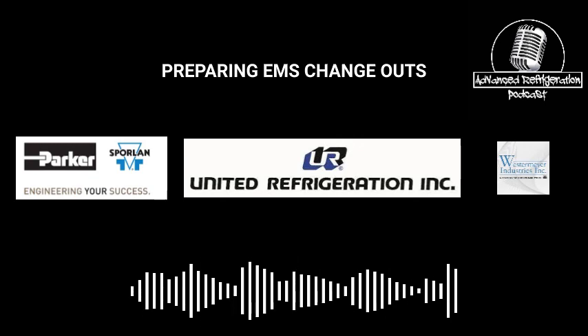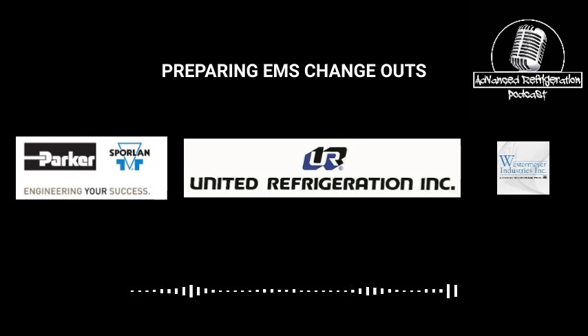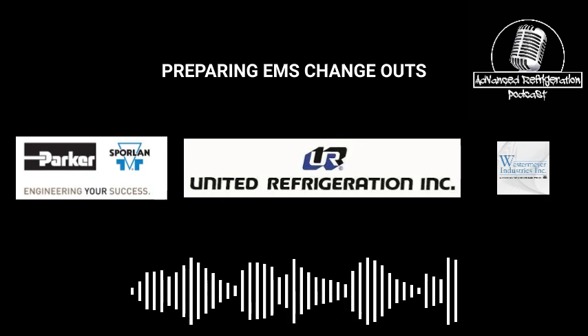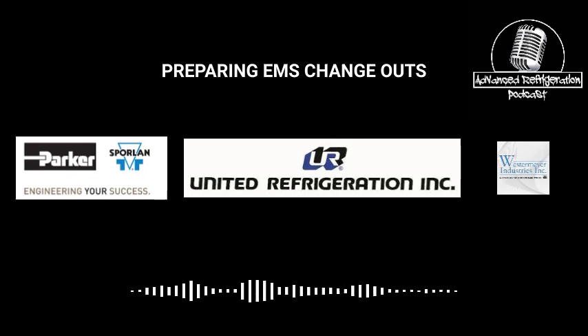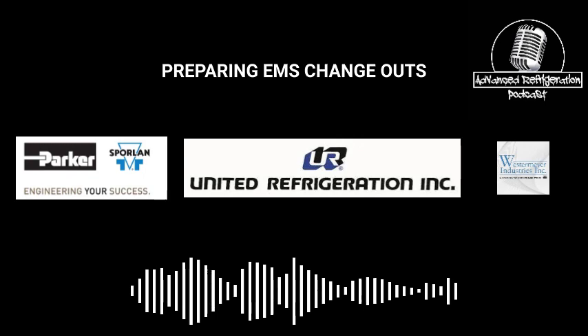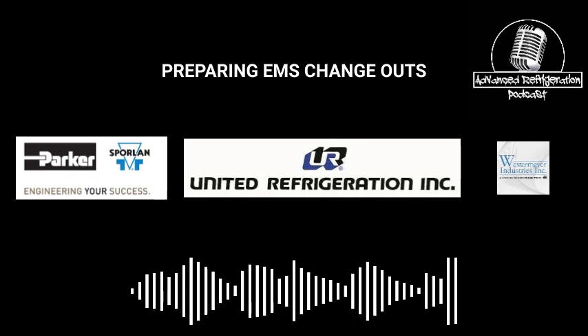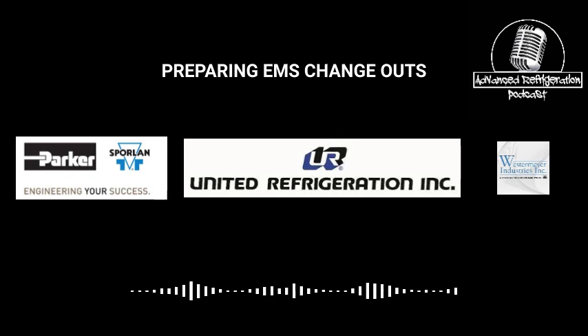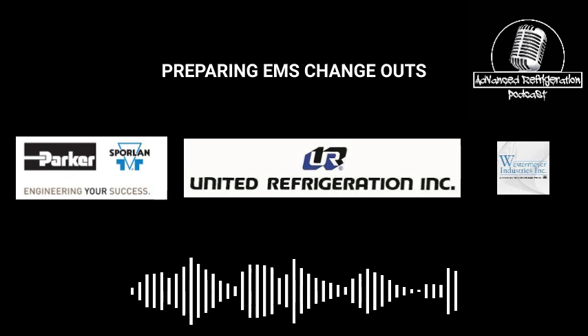One last thing is hot gas guys or electric defrost. You should be using 2 relays. You should be using a refrigeration relay and you should be using a defrost relay. Now, the way this should be set up is the normally open of the refrigeration relay should feed the common of the defrost relay. So that way, refrigeration has to be off and defrost has to be on in order for defrost to work. The reason this needs to be this way is you don't want the hot gas solenoid or the contactor to energize with the refrigeration on.